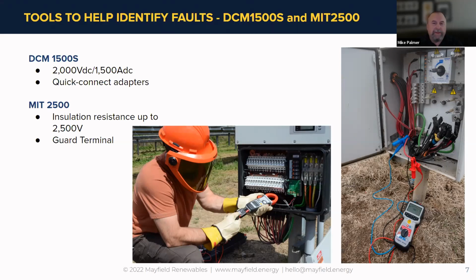And that's another reason for the MIT 2500 in a handheld. Obviously, you can do that test using a variable voltage unit, assign that 1500 volts and never go over that, because it will stress the cable. But think about what an array is doing over its lifespan. It's stressing the cable daily, with the activity from the sun and the energy we're producing. So it's not a cautionary thing for the cable. It's built to do that as long as we don't have any faults in it.